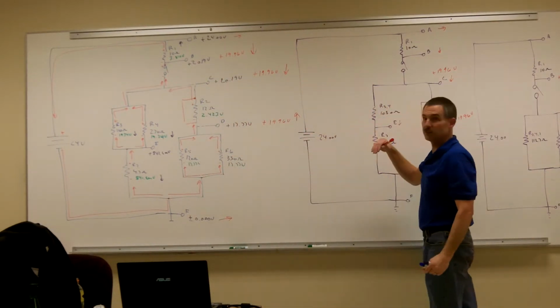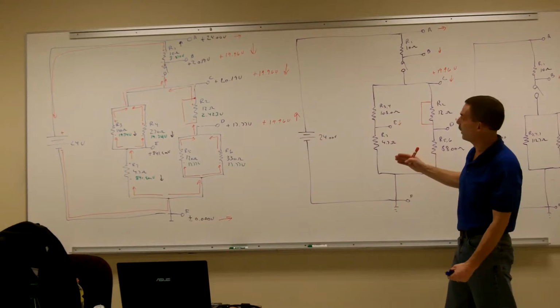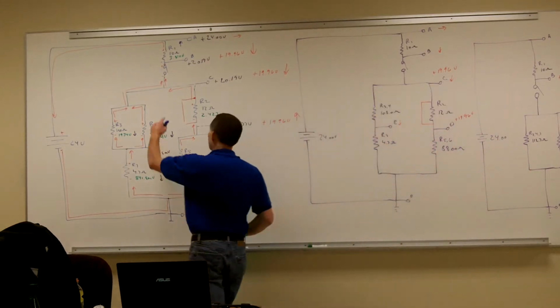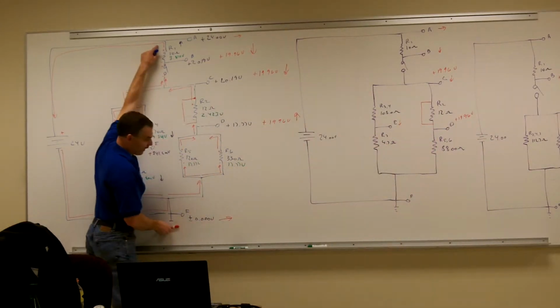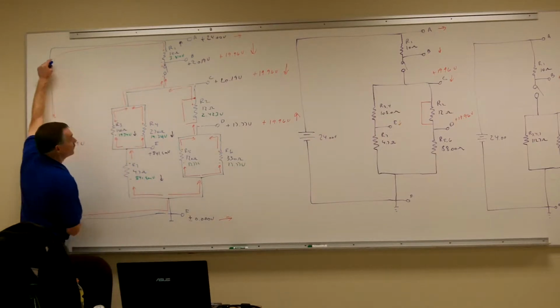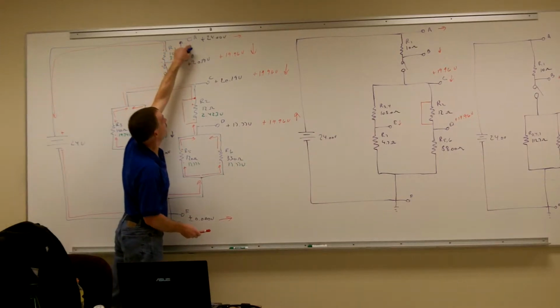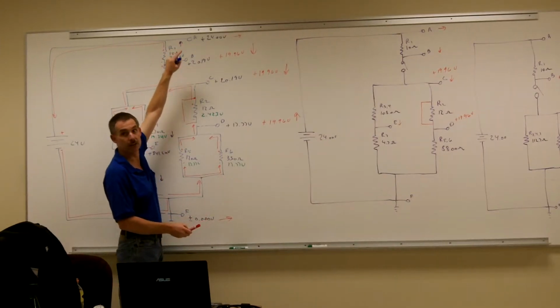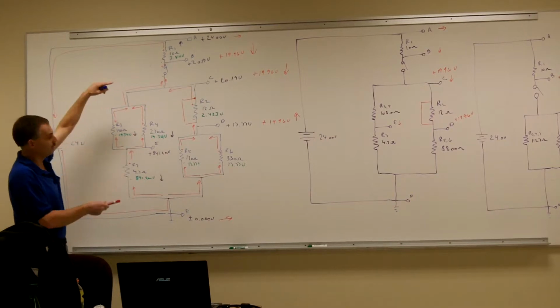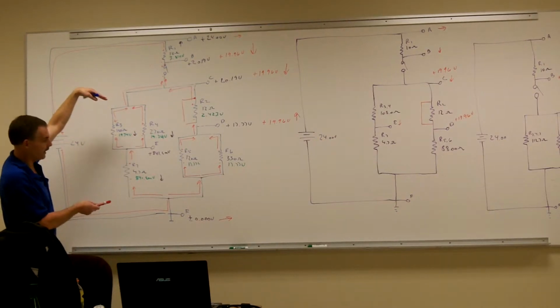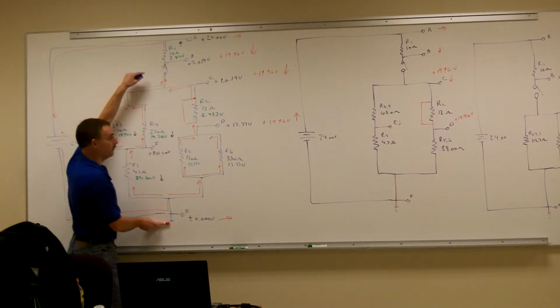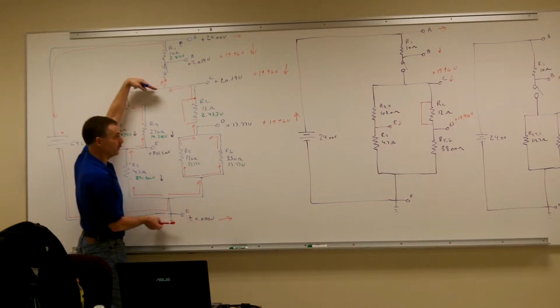So if you're really confused about what happened or where the problem went, draw the arrows. If you know that your test points A to F remain the same, you know that your source voltage is good. If something happened to your source voltage, test point A would have probably changed. Since test point A never changed and I'm referencing my ground, I know my source voltage is good.